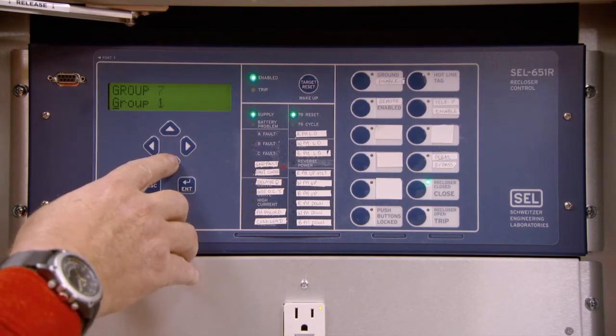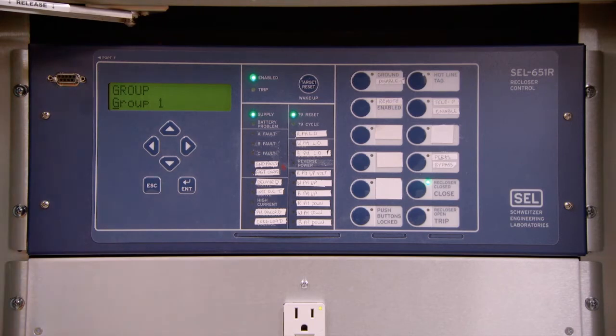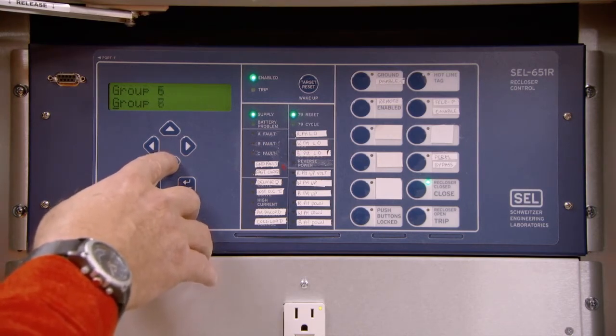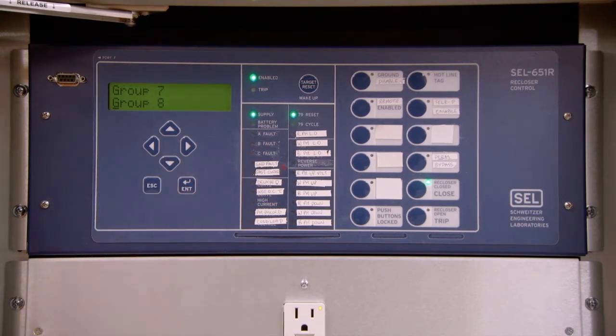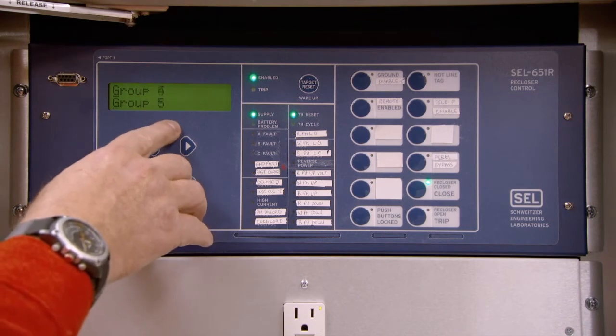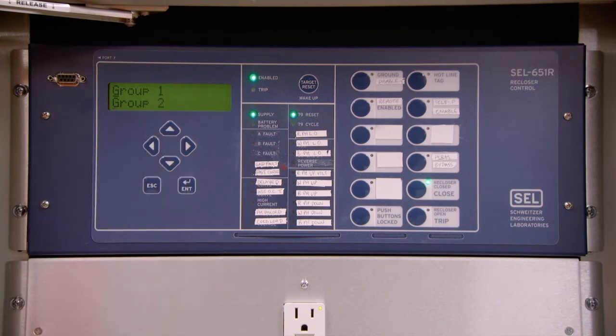This will display Group. There are 8 possible group settings. In the distribution world, it will typically be Group 1. There might be some advantages in generation connection that may allow for Group 2 to be programmed. With Group 1 selected, press Enter. This scrolling screen will now display the desired settings. In this case, identifier settings and instrument transformer settings.